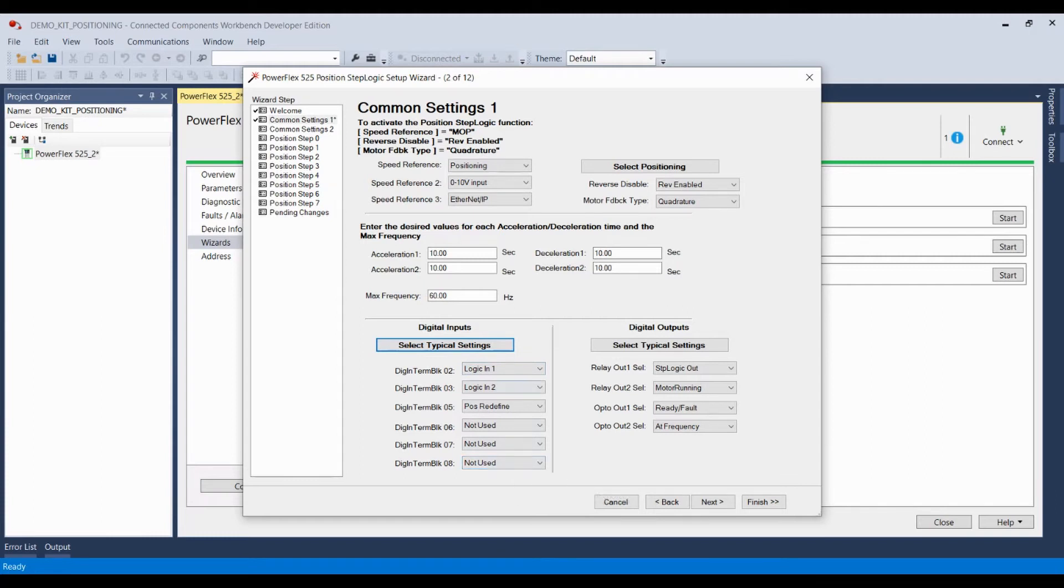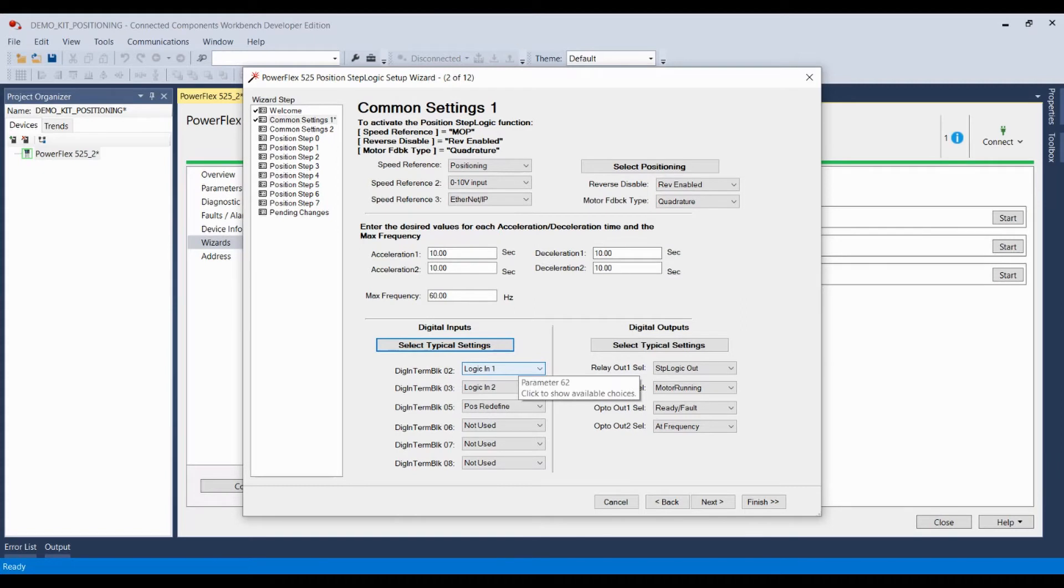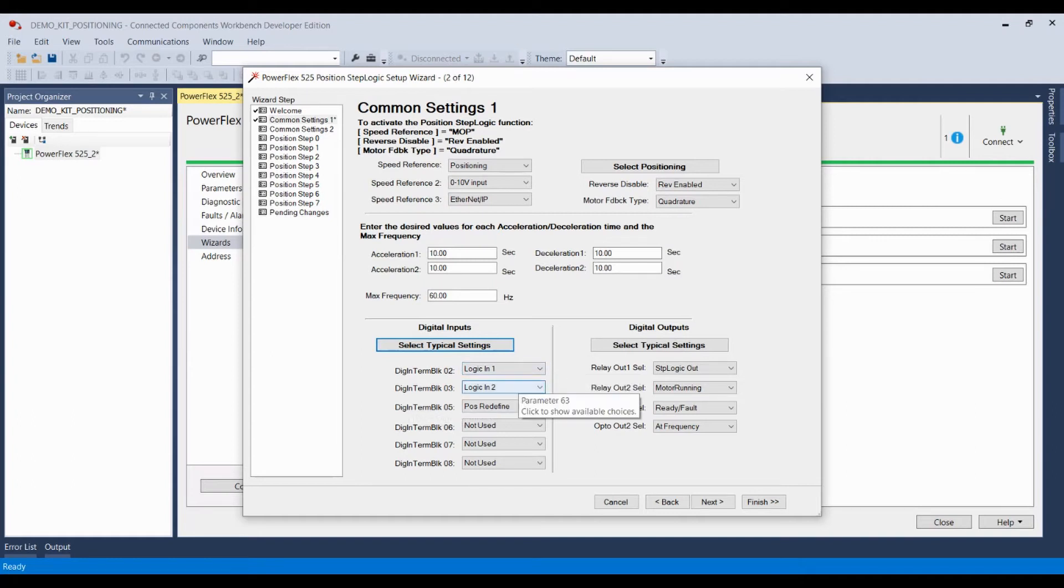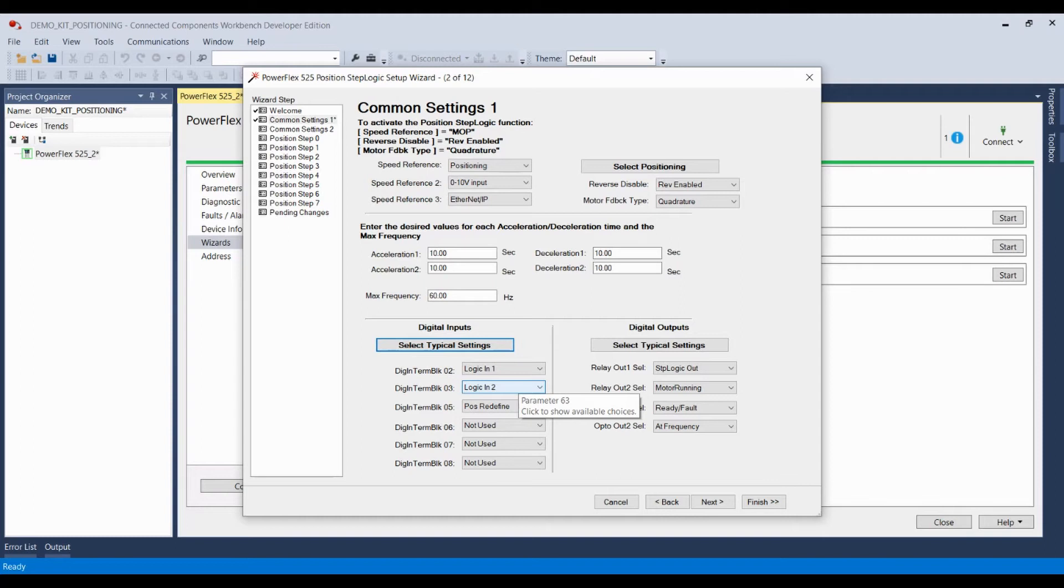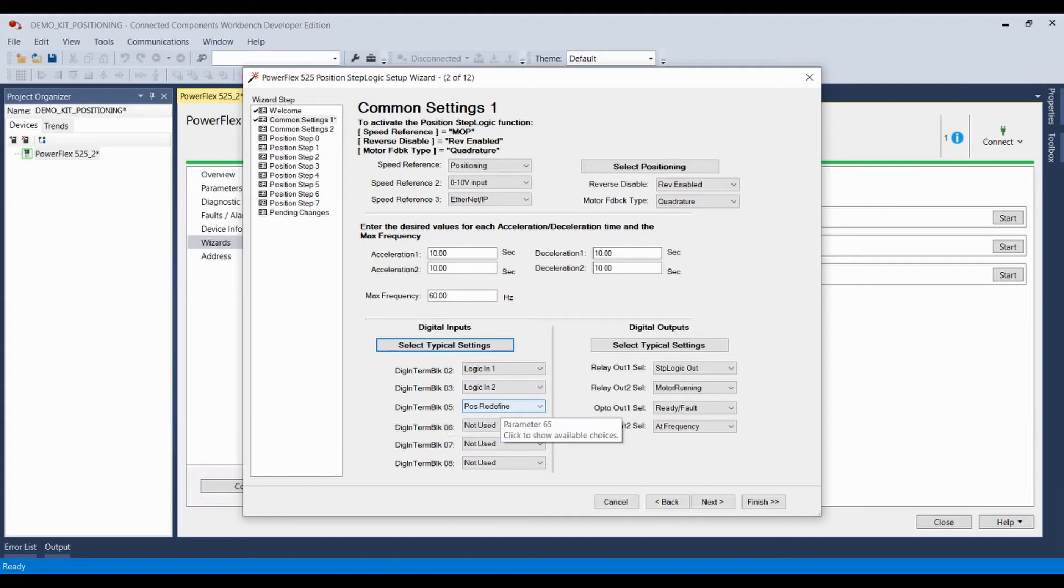I'm going to set digital terminal block two to logic input one. That's going to correlate to the position sensor, letting the system know that a receptacle is in place. And terminal block three, I'm going to make logic input two, which will let the system know that a dispense action has completed, which will allow the system to then run back to step zero to move another system into place.